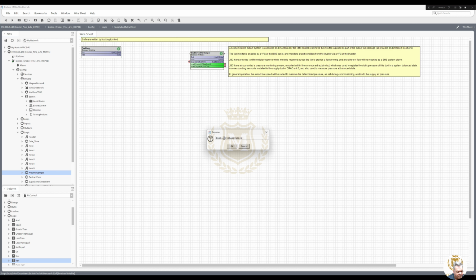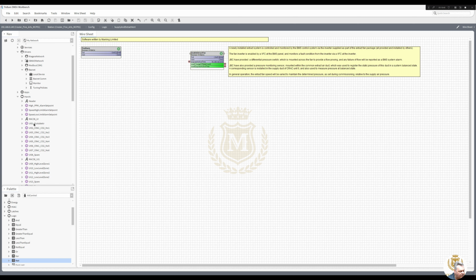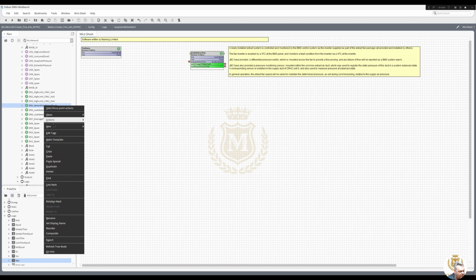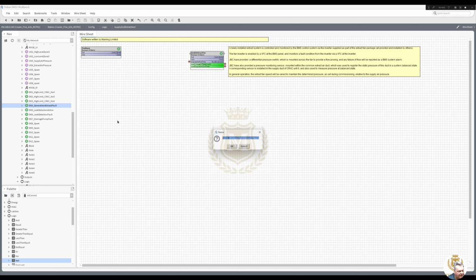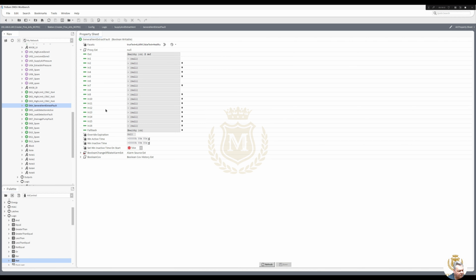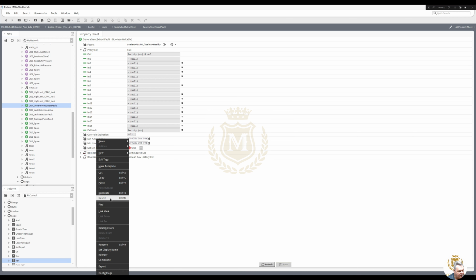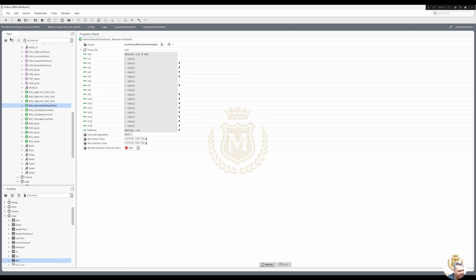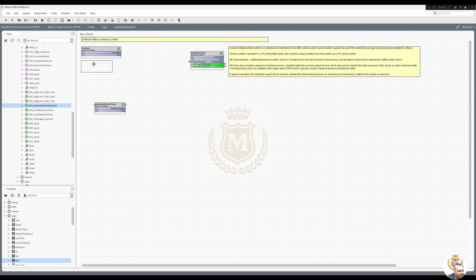Rename, enable, extract system, extract fan, enable extract fan. And it mentioned that we've got a fault. So if I go to my inputs and look for my fault for that, general vent extract fault, I'll just copy that, paste that into there. I need to take out any alarms that are on here because I don't want the alarms twice, and I don't want the history. So let's just delete the alarms and delete the history. So that's that one done.